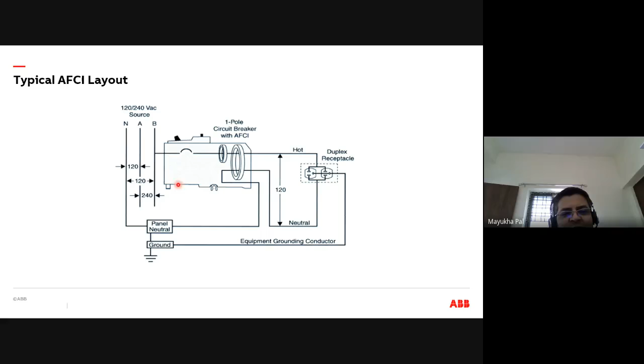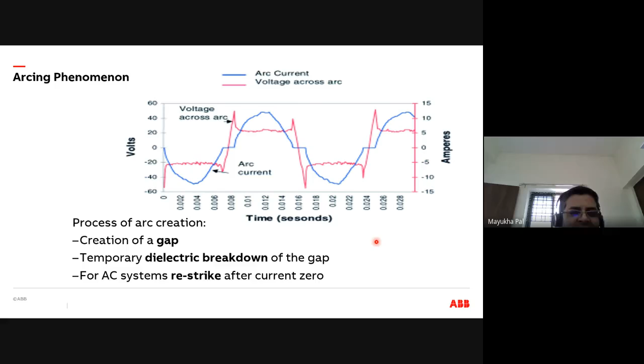So let's look into typical arcing phenomena. How do you define arc? If you look at voltage, current, and time, the blue one is the arc current, and the red one is the arc voltage. So the process of arc creation, or the arcing phenomenon, is because of the creation of a gap, or temporary dielectric breakdown of the gap, or a restriking after the zero cross. That's in an AC system. So these are the typical ways the arc is created. And if that gets amplified and reaches a hazardous level, that's what creates a lot of hazard. And that's really what I told in my first slide, how it severely impacts.